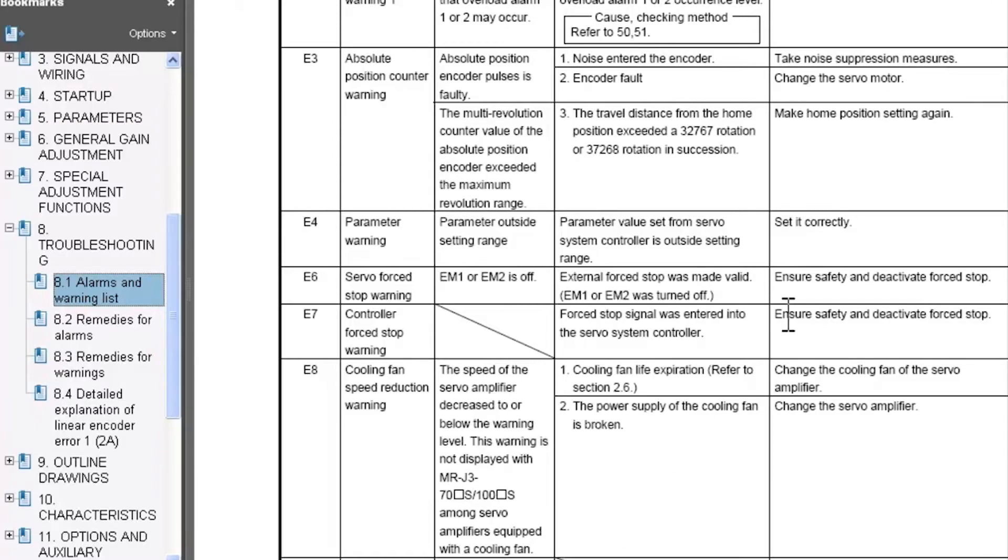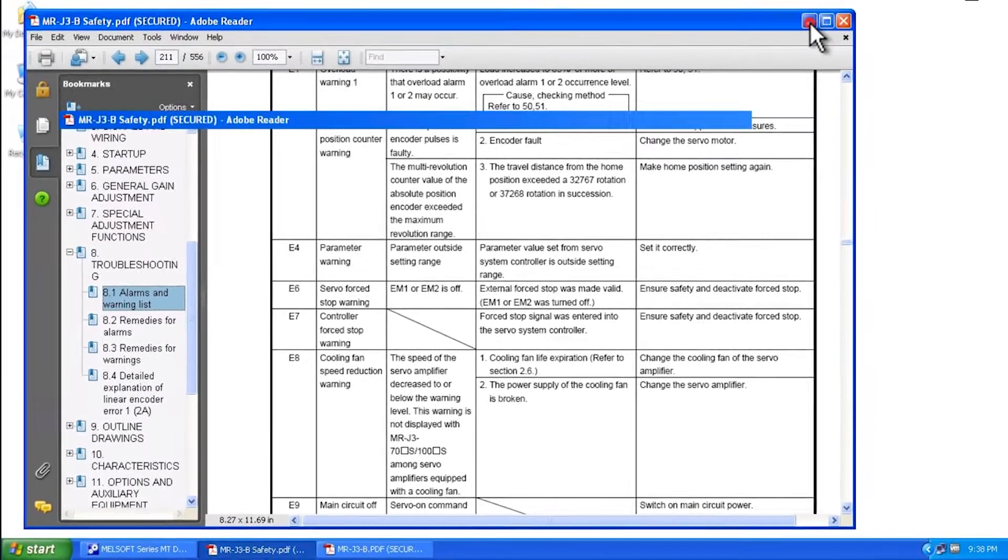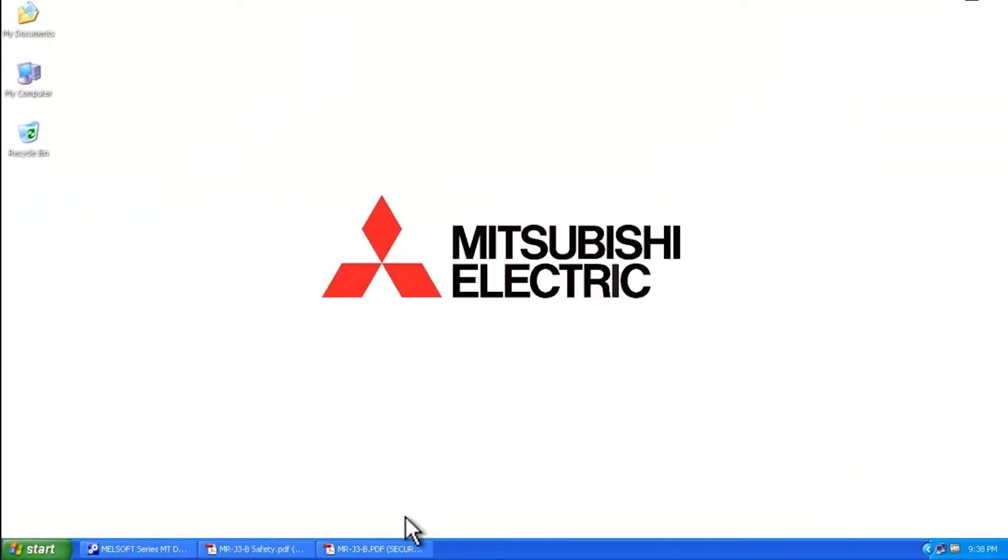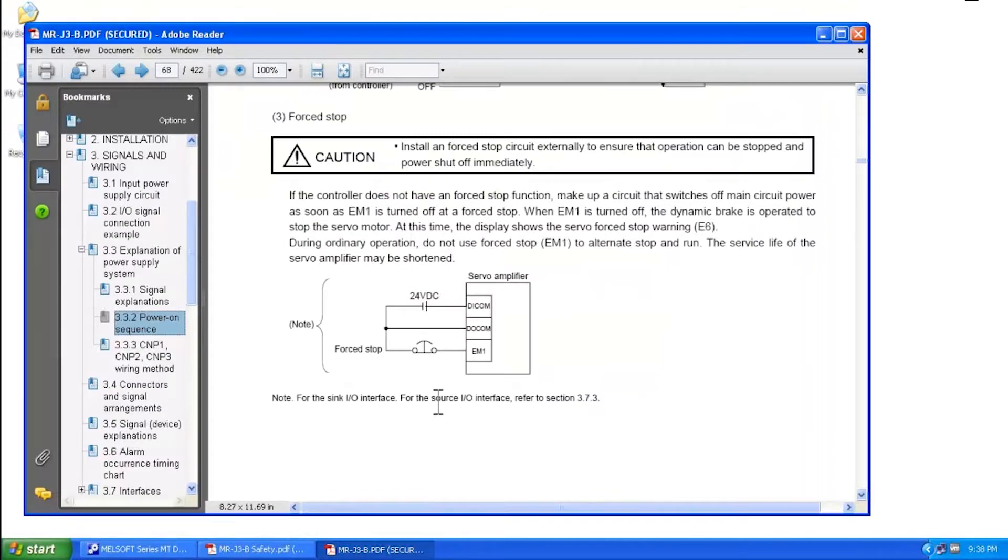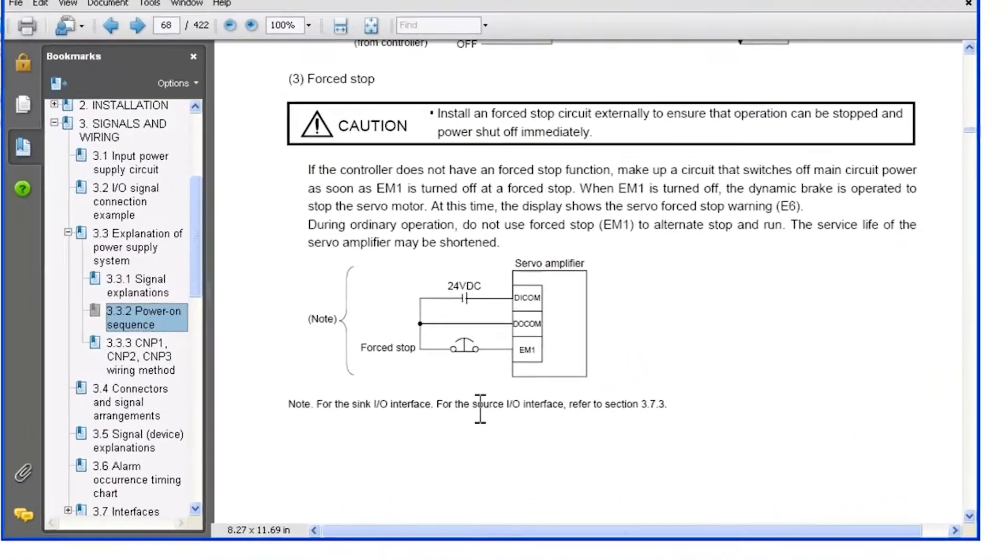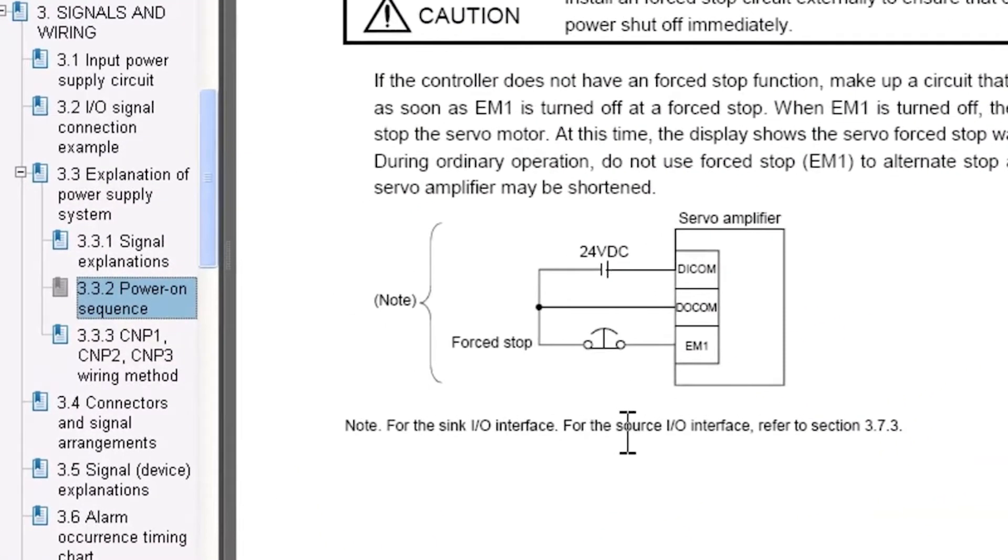First, let me show you through the physical wiring how you can disable the E6 warning message. Essentially what you have here is circuitry with a normally closed contact. You need to tie the negative end of 24 volts to the force stop signal into the EM1 signal on the amplifier.